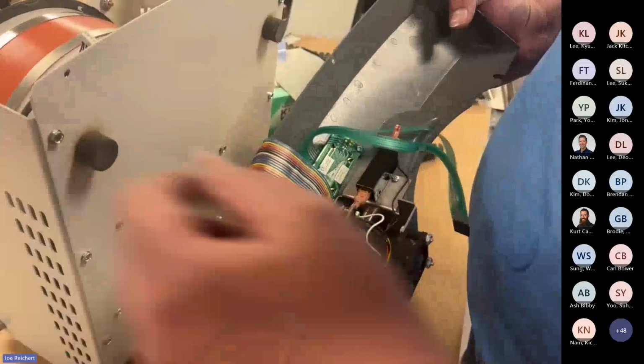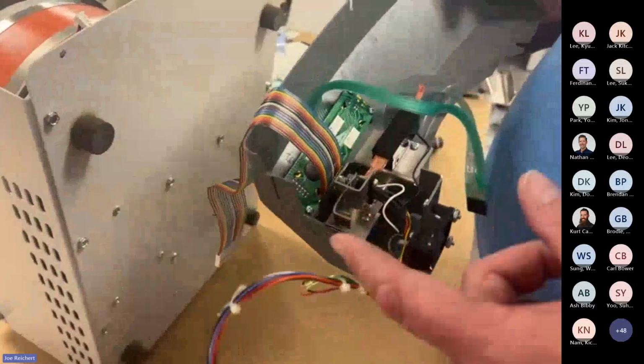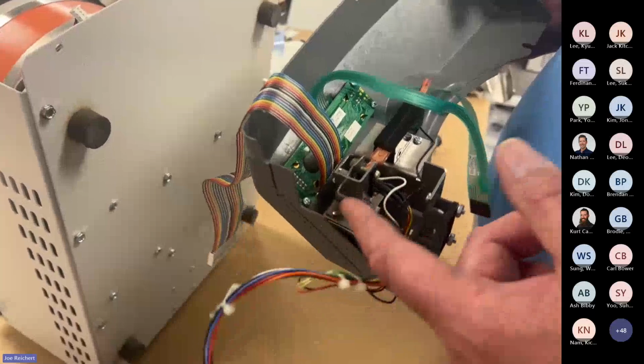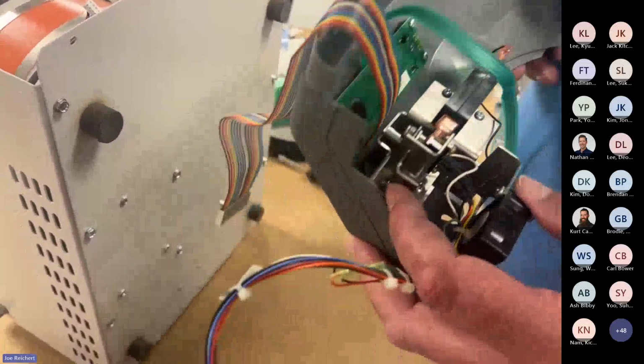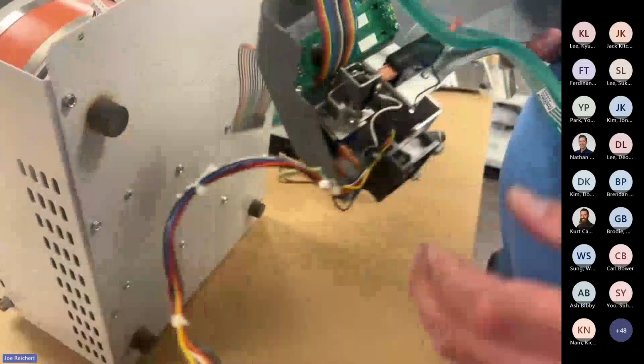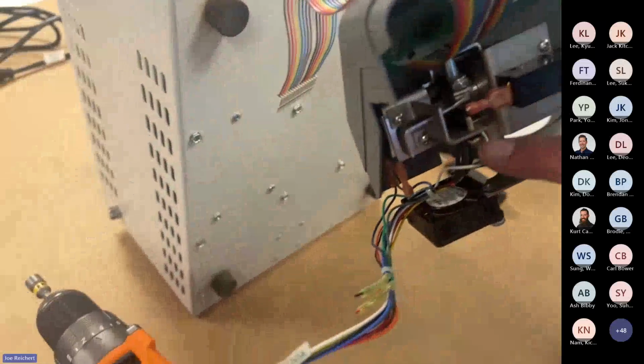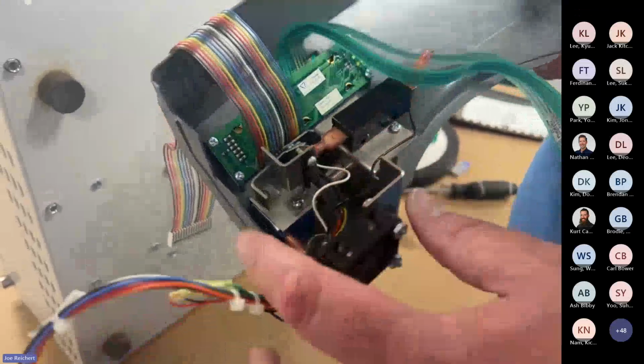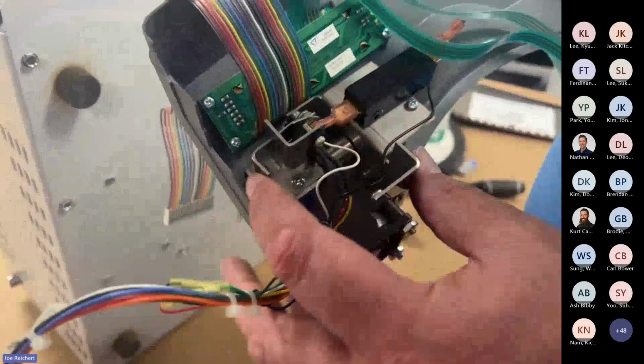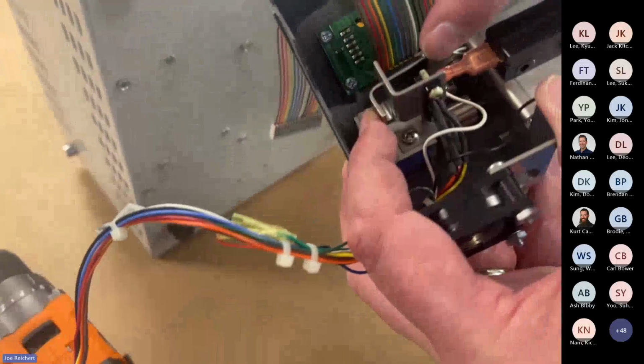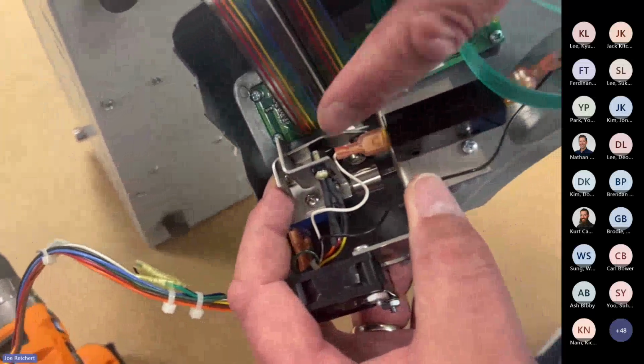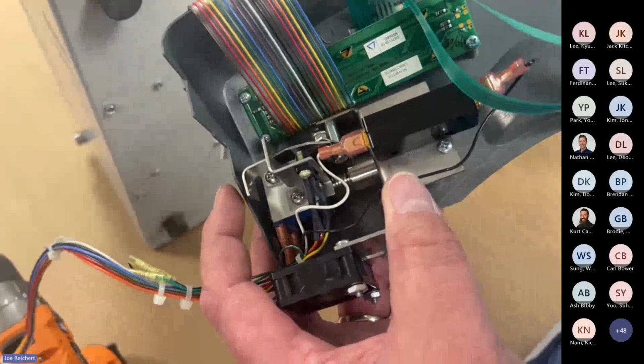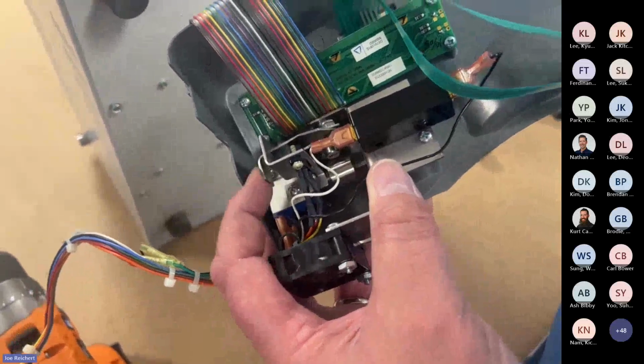On the inside again is that latch mechanism. When you put your screw through this little safety hole in the side, you're hitting this little lever here, and that's how you know it should be very free, shouldn't stick at all. The way the unit knows that the lid is closed, besides that switch, is it also has an optic eye, which is part of the latch here. It either sees its reflection or it doesn't. It might be hard to see on the camera, but there is a black painted piece right here on the steel so that it blocks the optical eye. And then here, opened, it sees its reflection from the shiny metal. So that's how it also knows that it's open and closed from that optic eye.